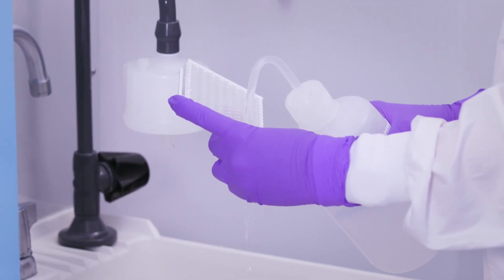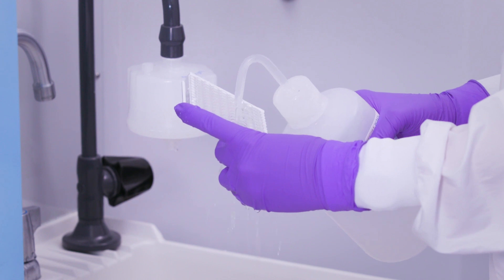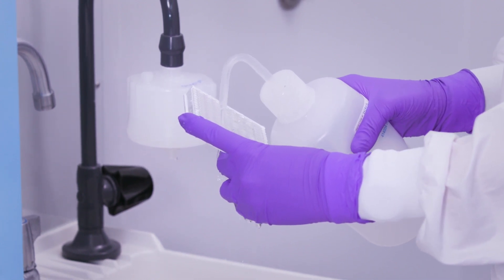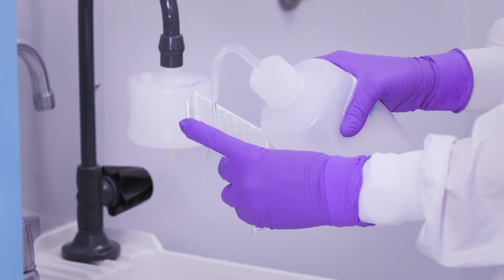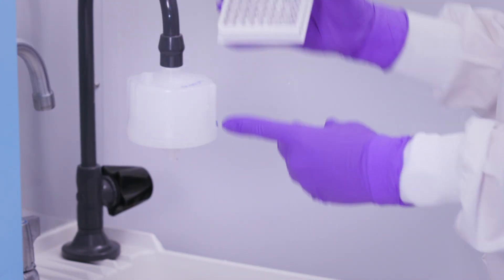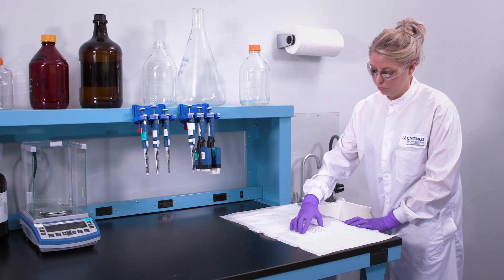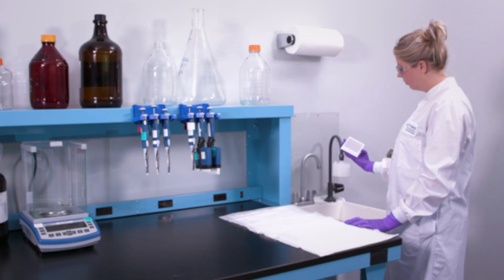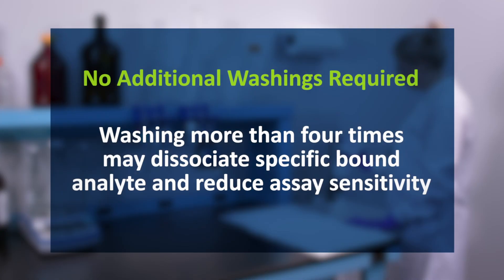With the second and fourth washes, start by adding the wash solution moving from the bottom toward the top of the plate. This ensures that the total dwell time of the wash solution will be essentially the same for all wells. Additional wash steps are not necessary. Doing this may dissociate specific bound analyte and reduce assay sensitivity.